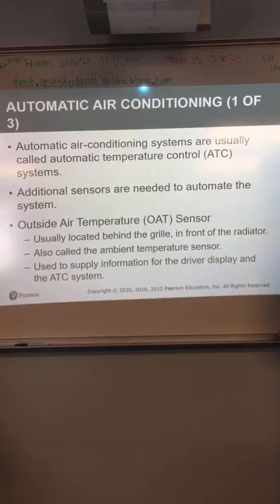Okay, so you get paid for the little stuff too? Yeah, you get paid for everything, there's a diagnosis involved. I didn't just go, well, that's what's wrong with it. Took a little bit to figure out. I checked the pressure and did all kinds of stuff before I got there. When everything else looked good and I couldn't figure out why the compressor wouldn't come on, I started looking at the scan tool data and found it was reading 40 below. We're like, well, that ain't right. So I found the sensor, found the plug, plugged it back in, and it worked. So you get an hour for diagnosis, an hour for the time to actually get to the connector. Yeah, you get paid for everything.